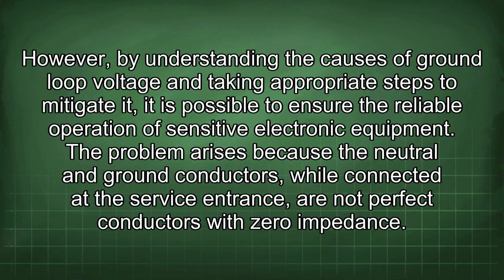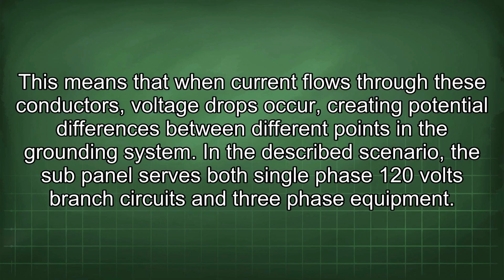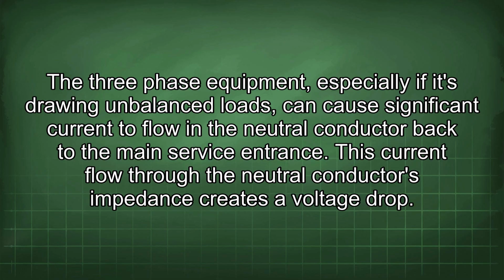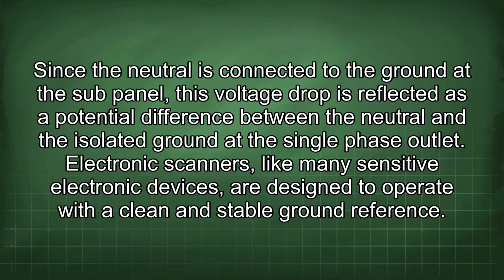The problem arises because the neutral and ground conductors, while connected at the service entrance, are not perfect conductors with zero impedance. This means that when current flows through these conductors, voltage drops occur, creating potential differences between different points in the grounding system. In the described scenario, the sub-panel serves both single-phase 120 volts branch circuits and three-phase equipment. The three-phase equipment, especially if it's drawing unbalanced loads, can cause significant current to flow in the neutral conductor back to the main service entrance. This current flow through the neutral conductor's impedance creates a voltage drop. Since the neutral is connected to the ground of the sub-panel, this voltage drop is reflected as a potential difference between the neutral and the isolated ground of the single-phase outlet.